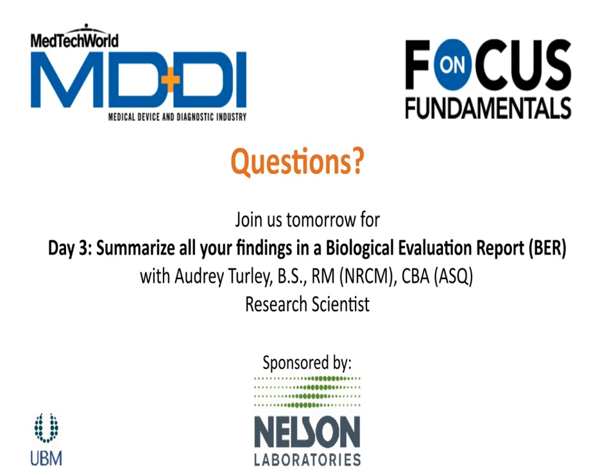That was the only component being changed, and say maybe you even have performed the full suite of recommended biocompatibility testing on the rest of the device. Now you do need to consider if adding this new component, any heat was applied or any new glue or any new manufacturing process, and really fully address the risk that could be posed to the patient.